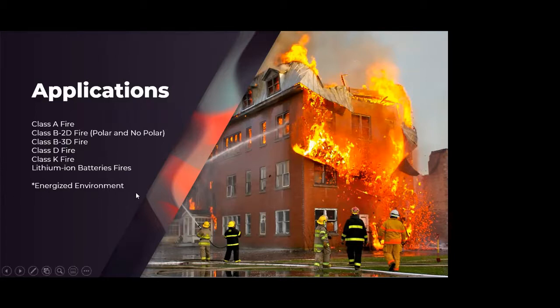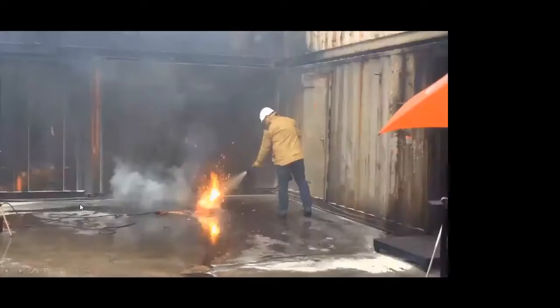I put energized environment on here too. I won't say we can use the agent directly on Class C, but we've done testing showing you can apply it onto three-dimensional Class B transformer fires in an energized environment. As long as you apply it at certain spray patterns and standoff distances, you won't get electricity feedback to the nozzles — that's why energized environment is listed here.